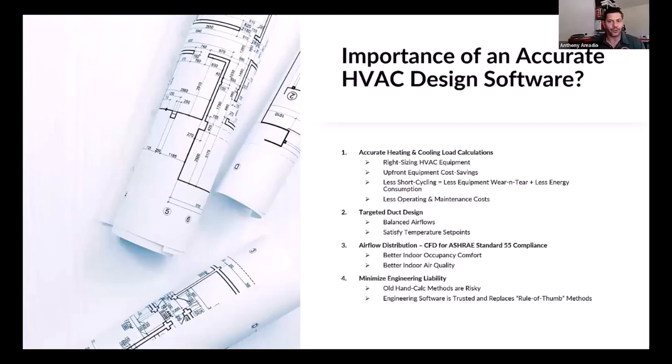But we do heat loss and heat gain calculations to right size equipment for many reasons. Probably a lot of you have heard, you don't want to oversize equipment. You'd be short cycling. You'd be wear and tearing your equipment. You'd be consuming a lot more energy. Of course, you don't want to undersize a system, or you won't meet heating and cooling conditions on design days.